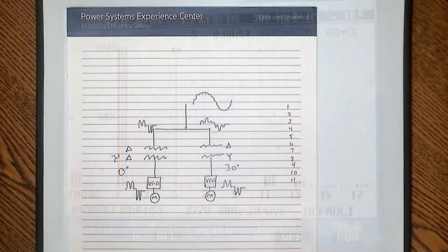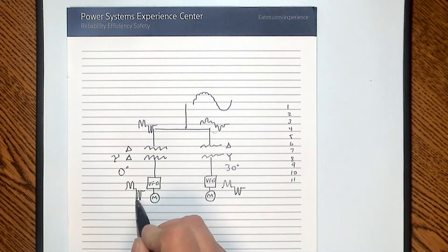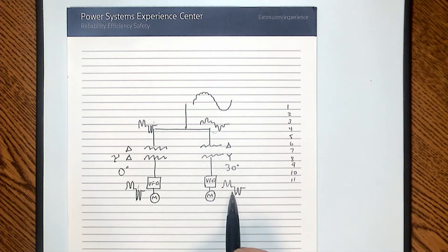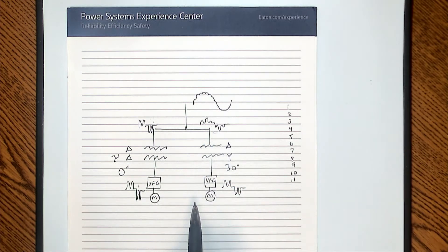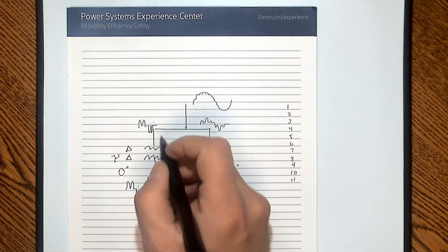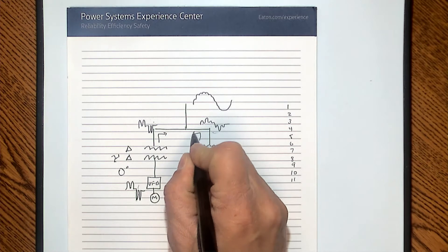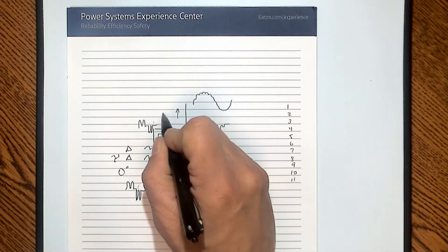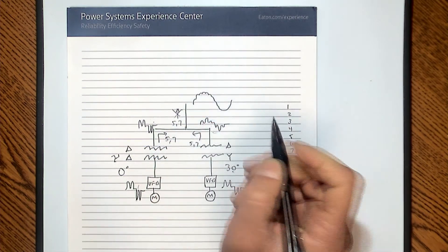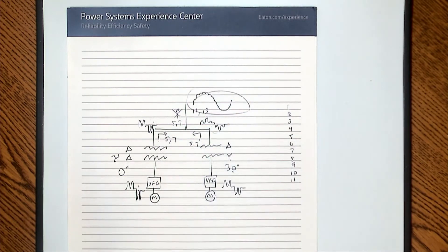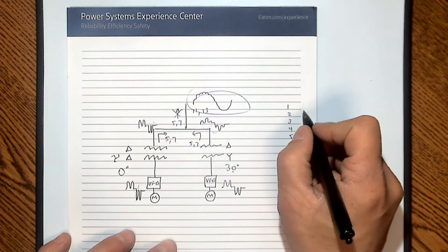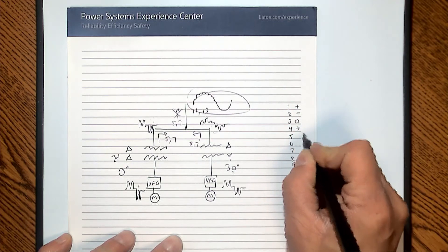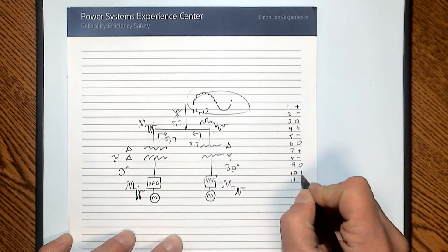Going back to the paper: with no phase shift on one side, the wave shape adds up similarly through the transformer. The other side has a 30 degree phase shift, so the wave shape changes. The fifth and seventh from the zero-degree side cancel with the fifth and seventh from the 30-degree side, so no fifth and seventh flow upstream — giving us the 12-pulse system. To understand how this works: for each harmonic order, the sequence follows positive, negative, zero — plus, minus, zero — and that pattern continues.